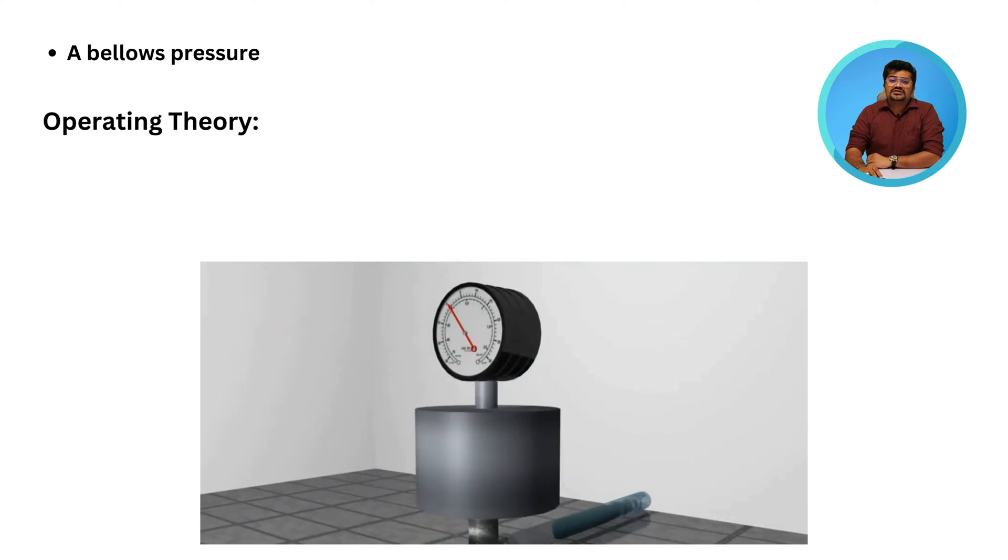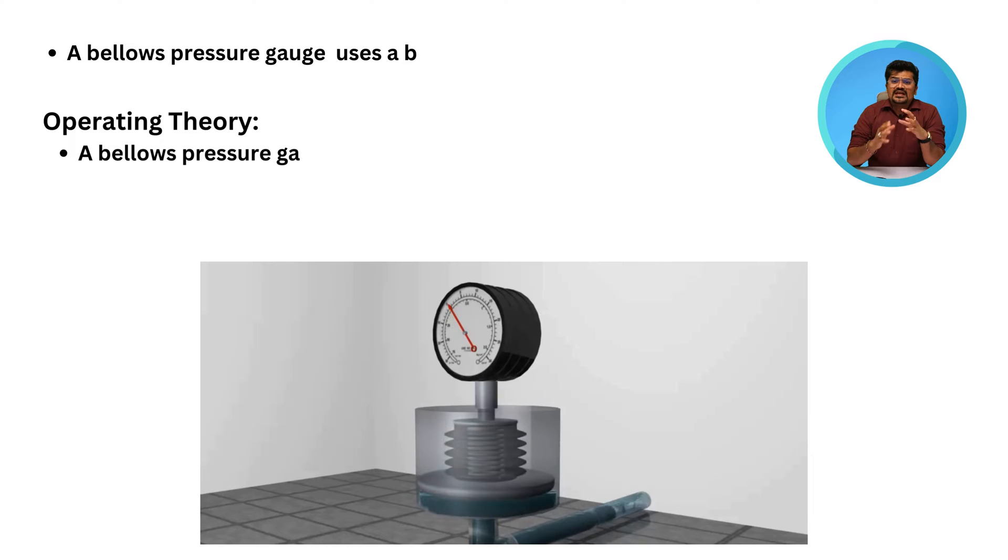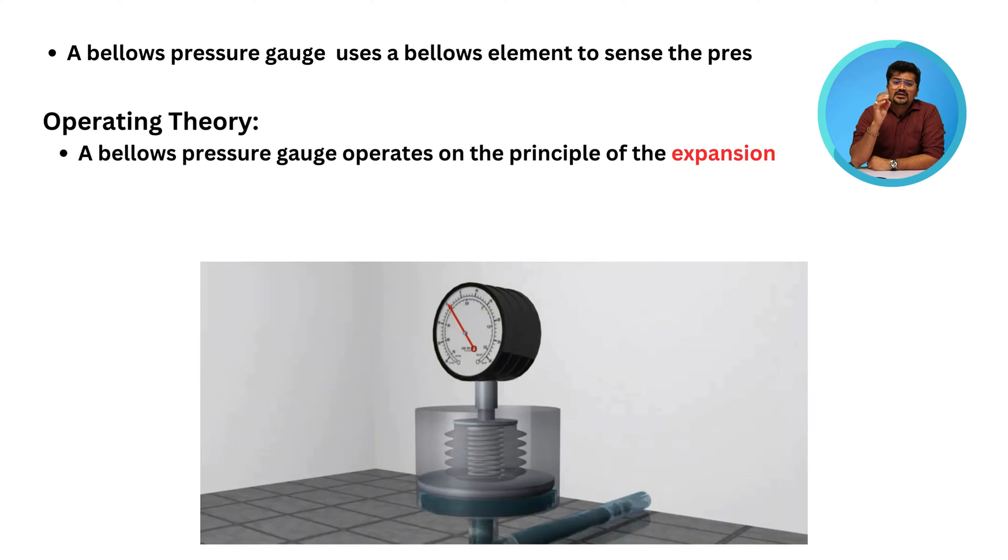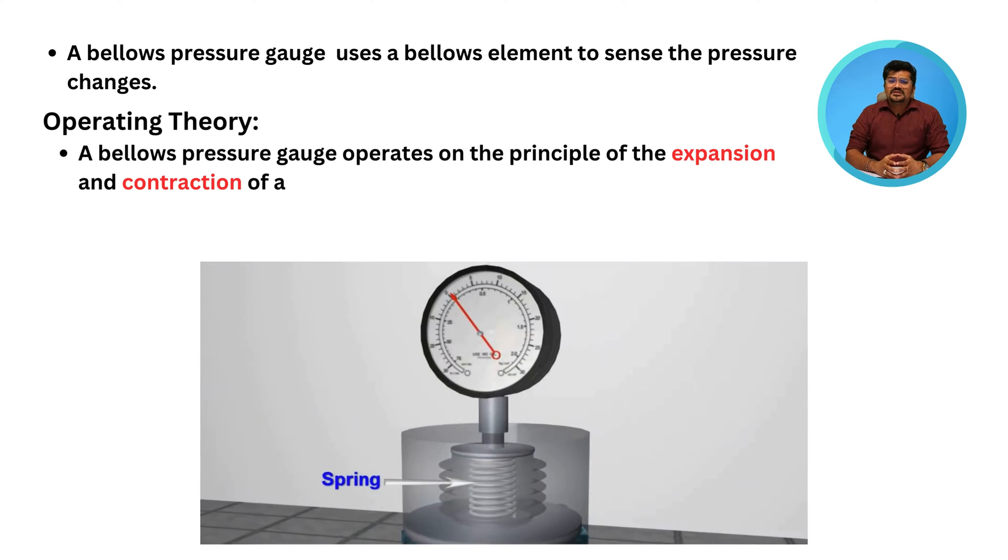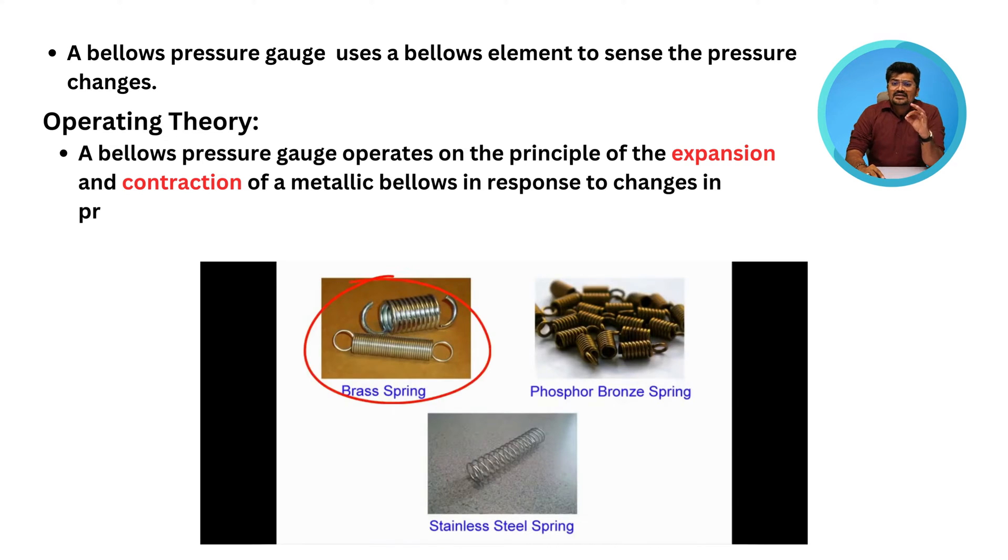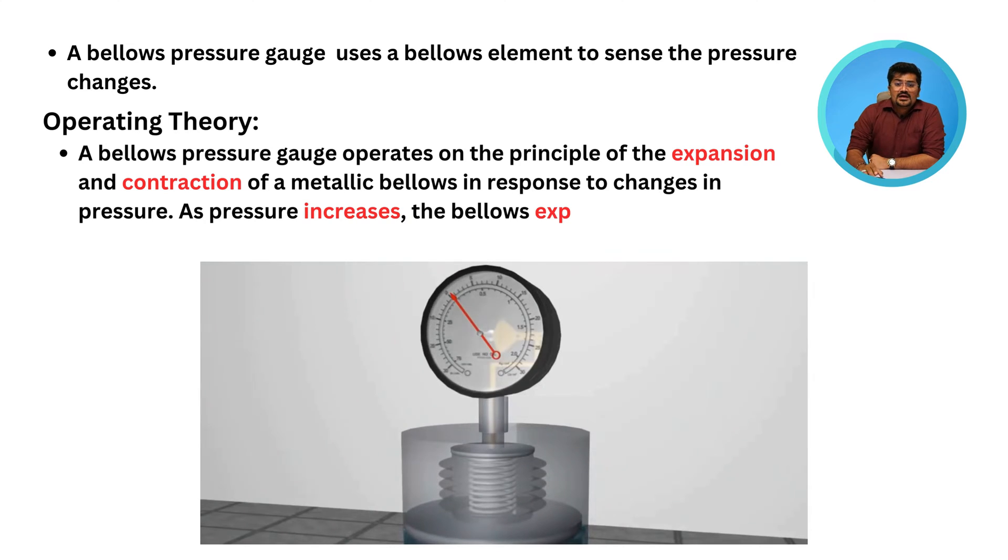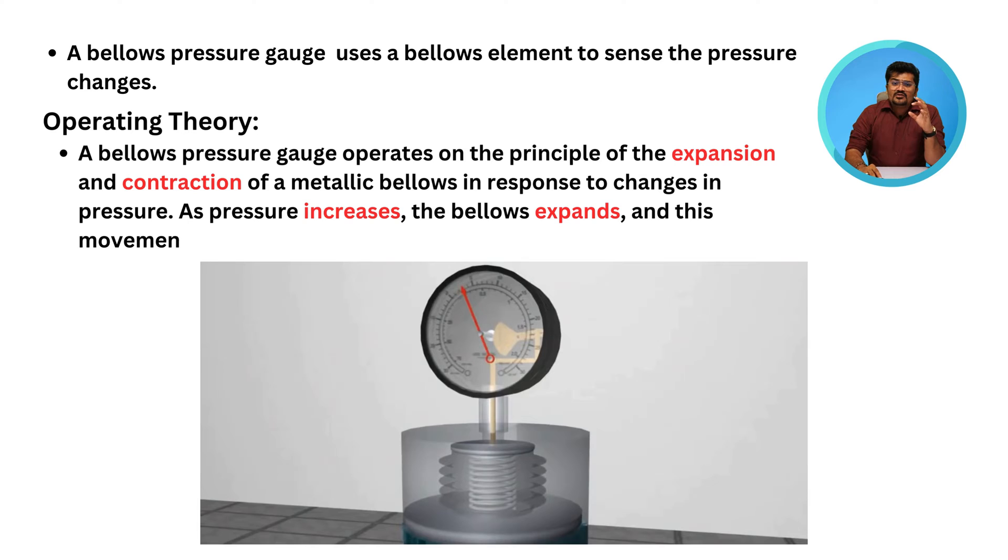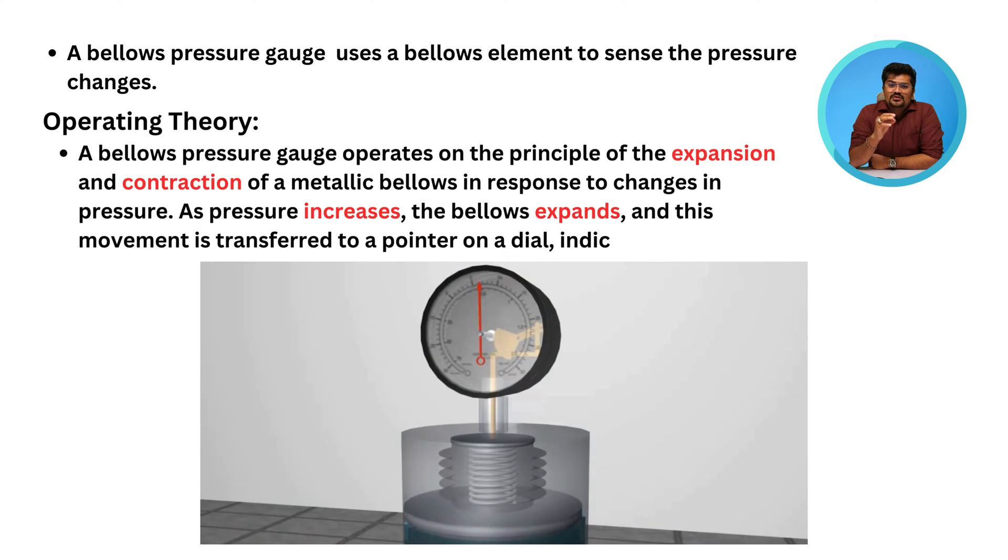A bellow pressure gauge uses a bellow element to sense pressure changes. It operates on the principle of expansion and contraction of a metallic bellows in response to pressure changes. As pressure increases, the bellow expands, and this movement is transferred to a pointer on a dial indicating the pressure.